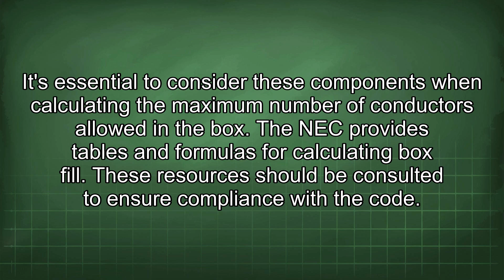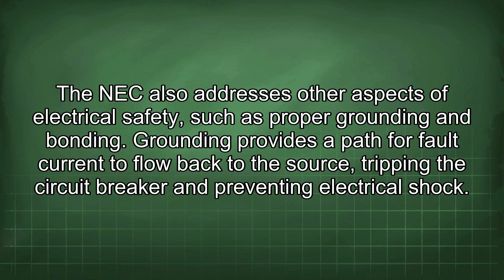These resources should be consulted to ensure compliance with the code. The NEC also addresses other aspects of electrical safety, such as proper grounding and bonding. Grounding provides a path for fault current to flow back to the source, tripping the circuit breaker and preventing electrical shock. Bonding ensures that all metal parts of an electrical system are electrically connected, reducing the risk of voltage differences and electrical shock.